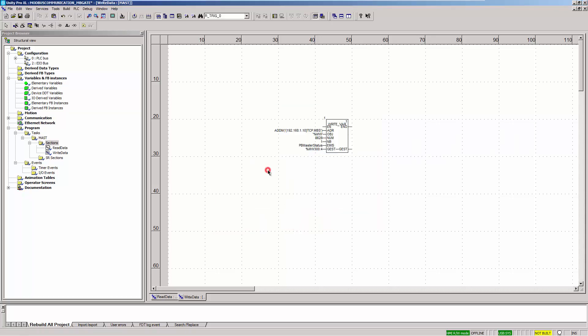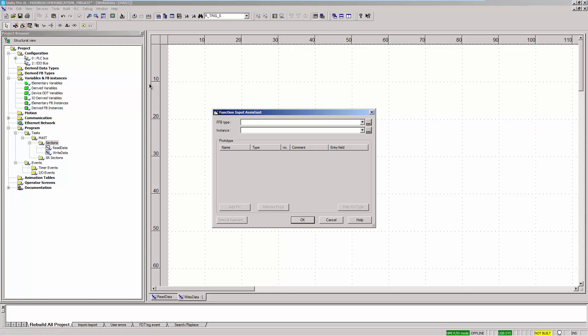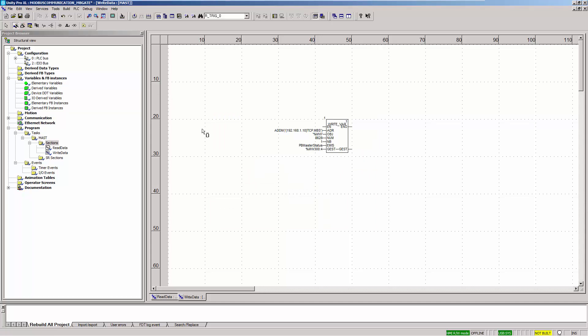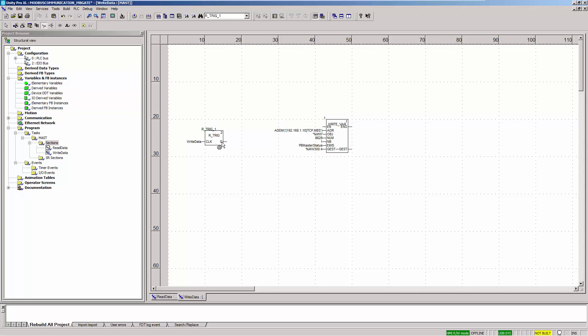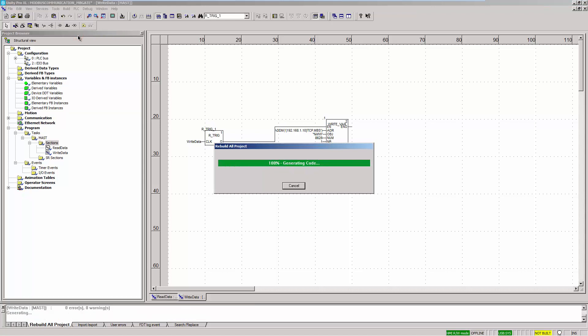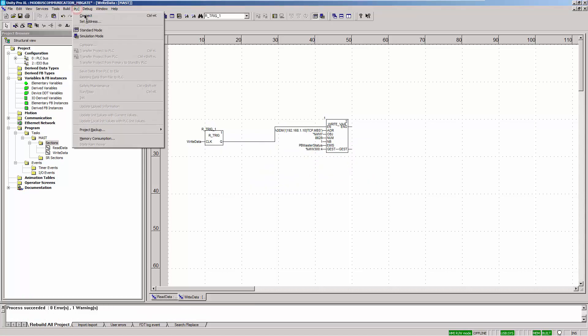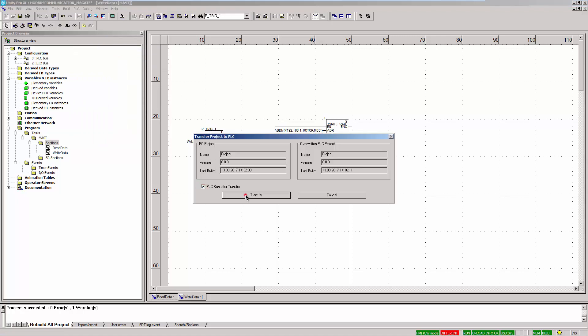Define the management parameter. To execute the function once, activate the optional input EN and add a function block R_TRIG. Define a variable for the input and connect the output accordingly. The WRITE_VAR function is executed once as soon as the input of the R_TRIG is set to 1. Now build the entire project, connect to the PLC, transfer the project to the PLC, and activate the option to run the PLC after the transfer.